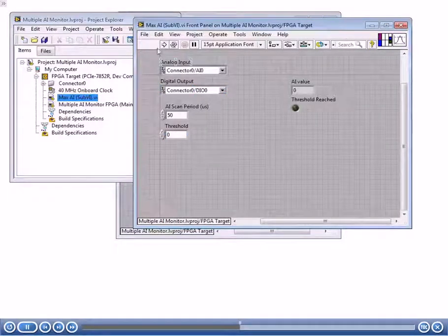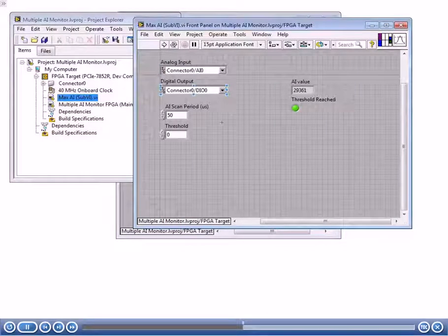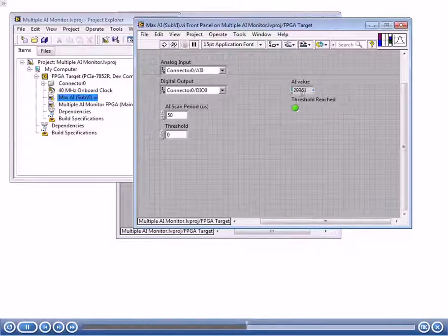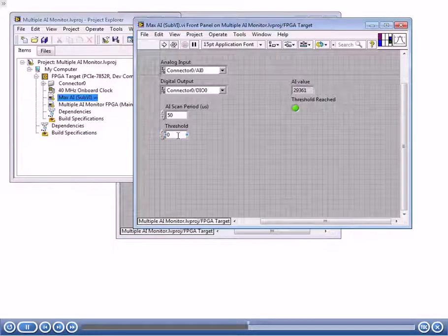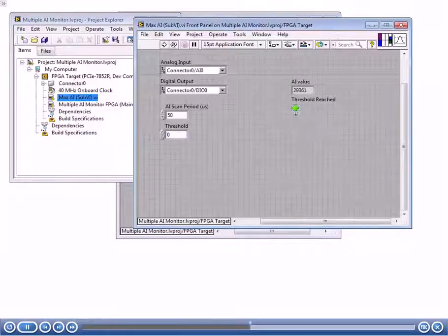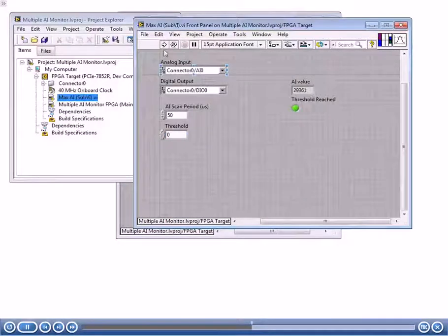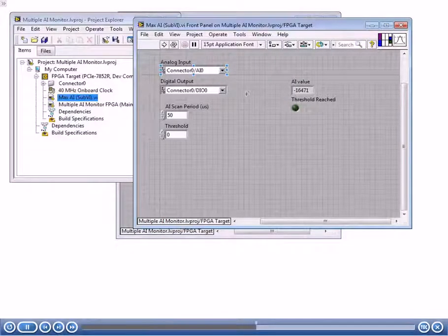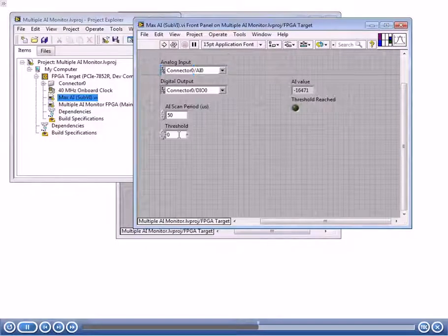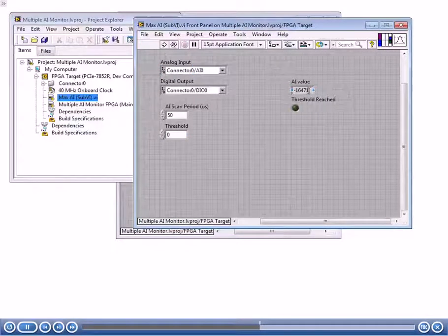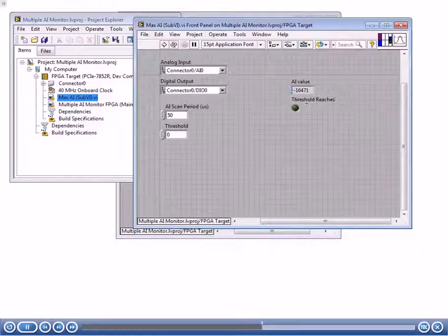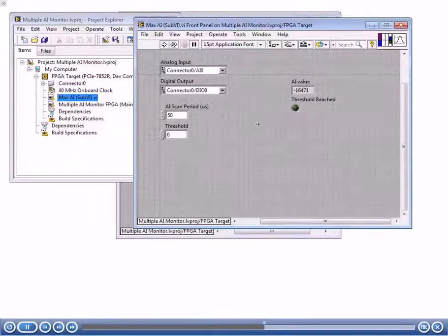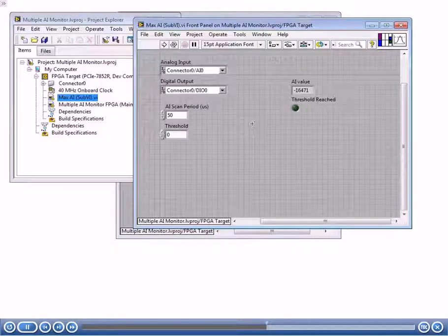It looks like our output that we got, our simulated I.O. from our analog input channel was 29361, which is greater than zero. So threshold reached is going to be true. Let me run it one more time. If you're creating a sub-VI, you can run it a couple times and make sure that in the simulated environment, everything's working okay. We have a threshold of zero. We have something that is below zero, negative 16471, and threshold reached is off. So for that quick test, it looks like everything's working all right.